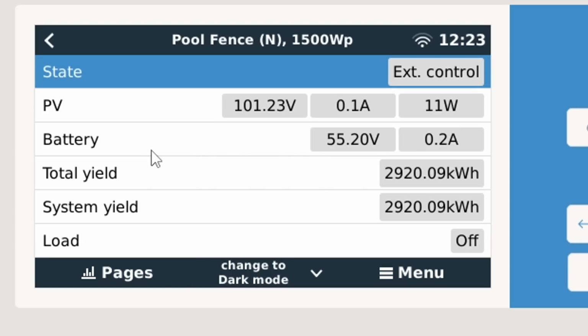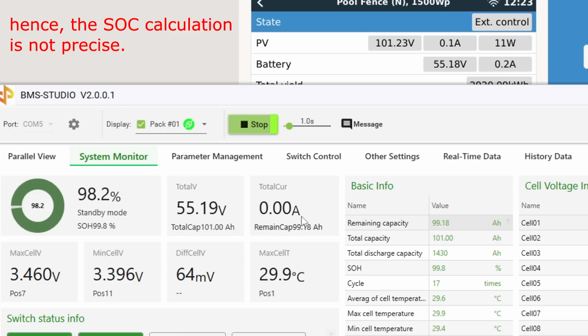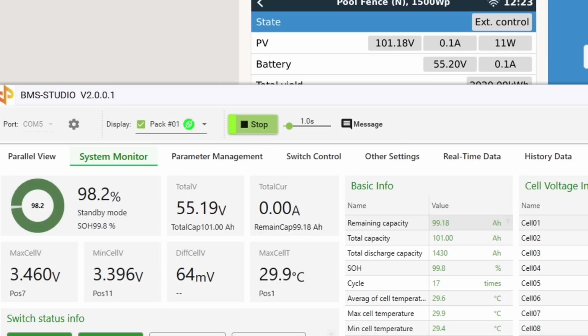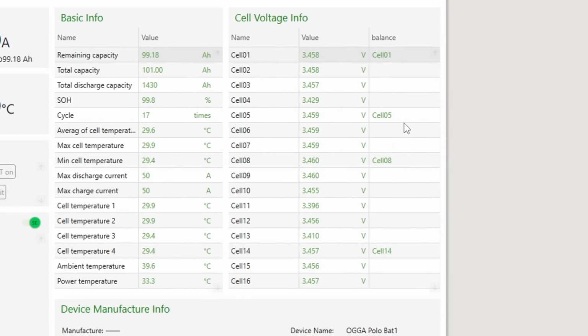It uses the voltage the BMS tells it. We can see that here - the battery tells the solar charge controller, hey, I'm on 55.19 volts, sometimes it pops up to 55.2, and we are still charging with 0.2 amps into this battery. But the BMS doesn't measure this anymore. This 0.1, 0.2 amps we see going into the battery is probably what's being used by the passive balancer - it discharges single cells with 0.2 amps, and this is what the solar charge controller just replenishes the battery with.